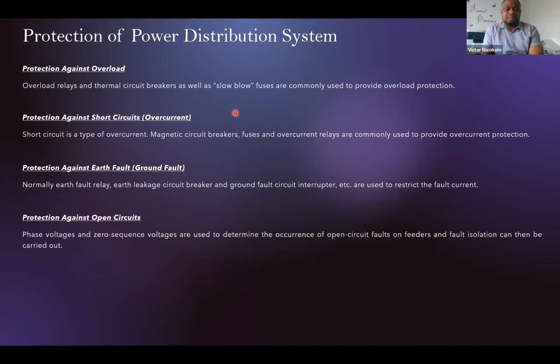Protection of power distribution system. I'm just going to touch on how we protect against those various faults we looked at earlier. Protecting against overload: overload typically operates on an inverse time curve, where tripping time becomes less as the current increases.